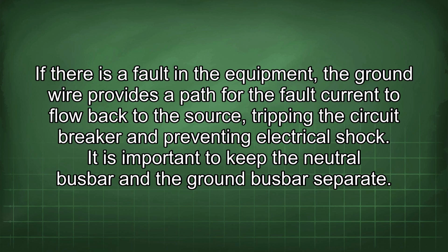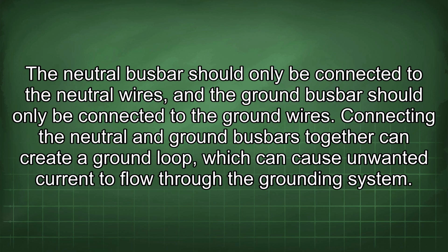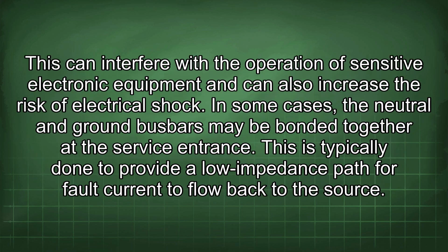It is important to keep the neutral busbar and the ground busbar separate. The neutral busbar should only be connected to the neutral wires, and the ground busbar should only be connected to the ground wires. Connecting the neutral and ground busbars together can create a ground loop, which can cause unwanted current to flow through the grounding system. This can interfere with the operation of sensitive electronic equipment and can also increase the risk of electrical shock.